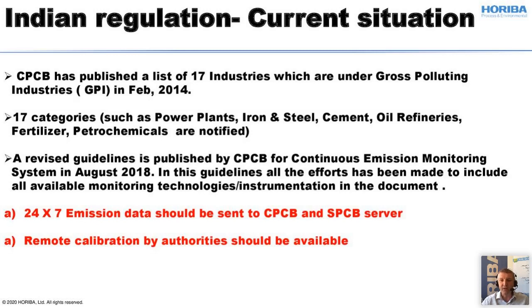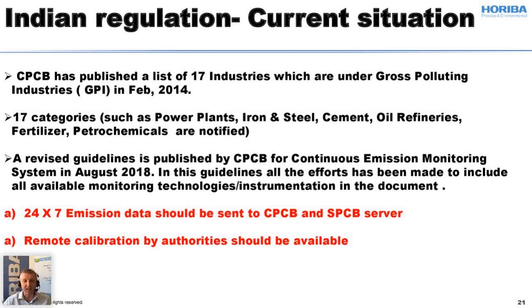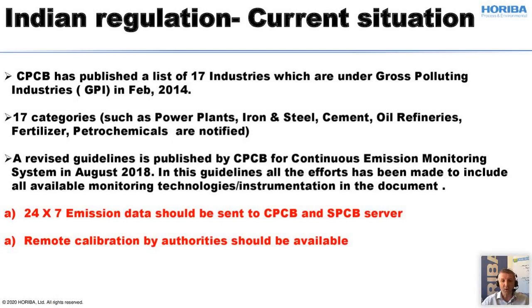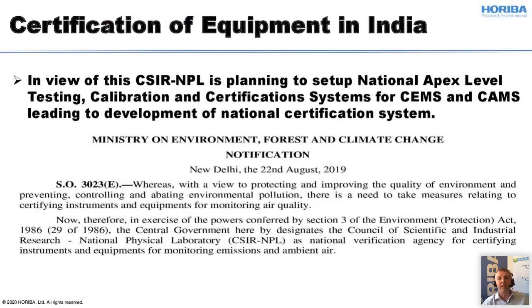With rapid industrialization, it is becoming a need and necessity to regulate compliance by industries with minimal local inspection of industrial sites. In August 2018, the CPCB published revised guidelines for continuous emission monitoring systems. This includes the submission of emission data every day all along the year to the servers of the CPCB and the SPCB. Furthermore, the authorities will have the possibility of doing remote calibration of the systems to ensure a correct analysis of the monitoring device. To achieve the same level of instrument testing and certification in India as it is already in Europe or the US, the next steps are already planned and published.